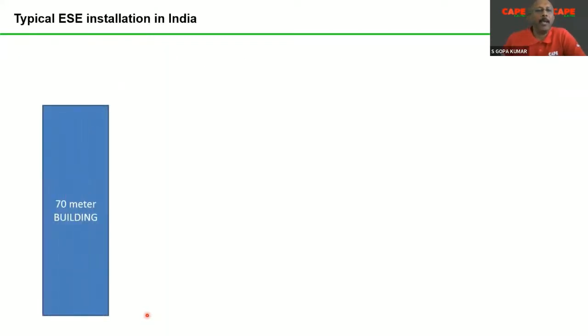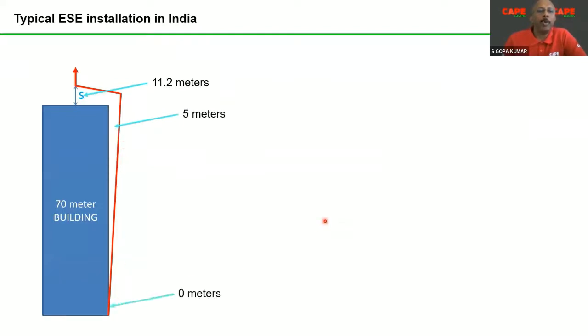That means if you look at the actual scenario, for a 70-meter building the air termination and the down conductor have to be physically away from the building. How much physically away? 11.2 meters physically away from the building. That means you have to have some kind of isolated or insulated material between the red line and the building. The red line is nothing but the parts of lightning protection. And the distance keeps reducing as we reach towards the bottom, for example 5 meters, and at the bottom of the building 0 meters if equipotential bonding is made. If it is not made, of course all these calculations are wrong.